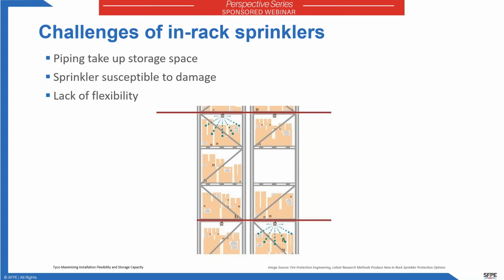However, no one seems to like in-rack sprinklers in terms of the warehouse operators. Through the years, I've talked to a lot of people running warehouses, and what they tell me is you've got to get these sprinklers out of the racks. They're susceptible to damage. They take up storage space. I can't move my racks easily. Got to get these sprinklers out of the racks.